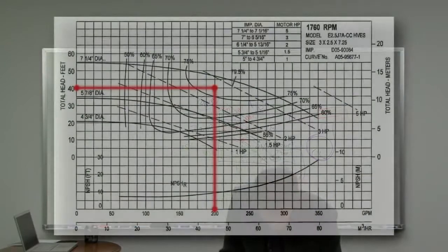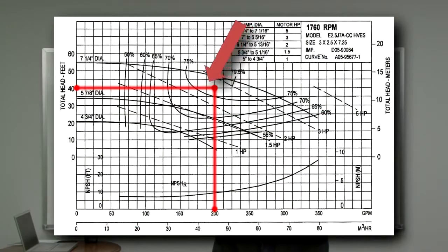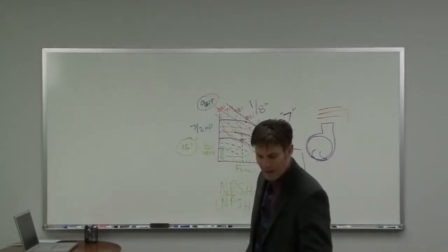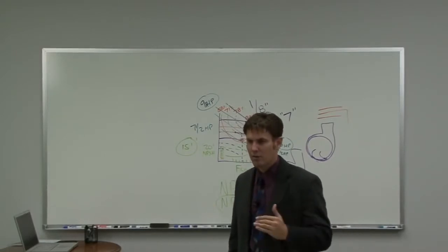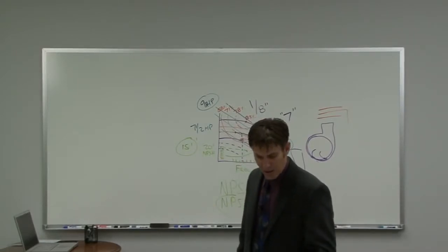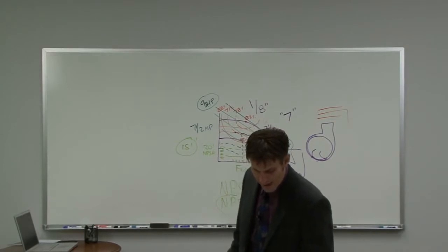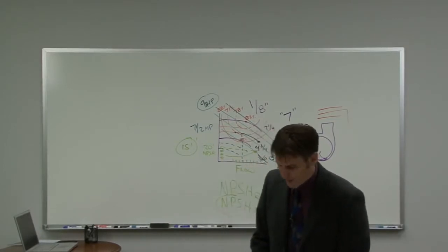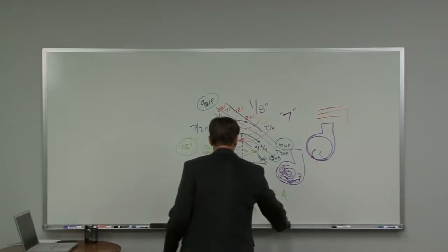So just eyeballing this, I'm about a half there and maybe one more half. So you might be somewhere around 6 3/4 of a diameter, maybe 6 7/8 of a diameter trim. You're going to be somewhere there. So that's what the manufacturer is going to trim that impeller down to if you don't tell them otherwise. They'll trim that impeller down to that size, and then we could draw a line, and we'll do that up here on the board.